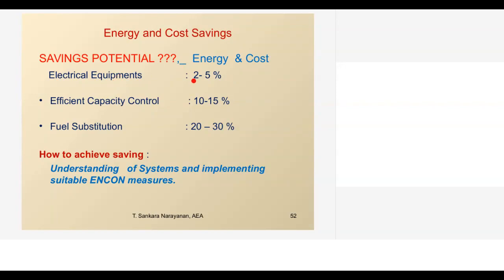If you are attempting only pure electrical equipment like network systems, transformers, and distribution systems, we may get around 2 to 5% reduction only. Wherever we are able to attack capacity control or change it to energy efficient capacity control, the saving margin can go up to 15%. With fuel substitution we will get a higher saving margin. These margins are only indicators, but technically, wherever potential is there, the auditor has to evaluate it. Then once the fuel cost changes, certain recommendations can be implemented a little later. So how to achieve saving: understanding of the system and implementing suitable ENCON measures. Today, if you ask for all the energy saving measures, we can put them in 2 slides. But the real challenge is which measure is applicable for which type of industry. There, one has to do a detailed analysis. Up to this, I have covered most of the things. I am open to questions.